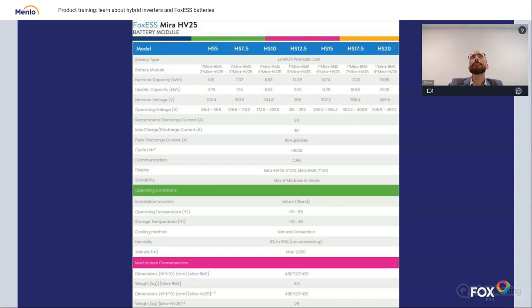Here you can see a minimal stack of 2 Mira batteries with 1 Mira BMS. This stack outputs 100 volts and can hold up to 5 kilowatt hours of energy. It can also output a bit more if it's needed, but of course within this 30-second time limit. Here you go. There is a writer's mistake. Here, those 4,000 cycles should be 6,000 cycles, and that's the only one. Sorry for that.